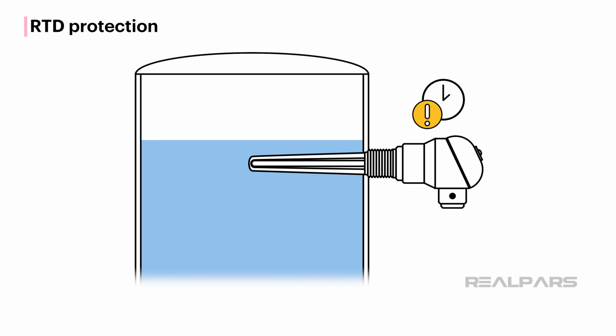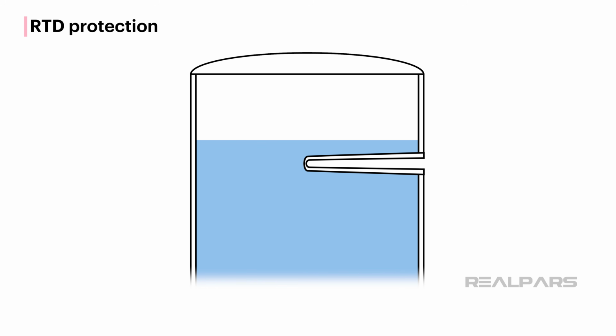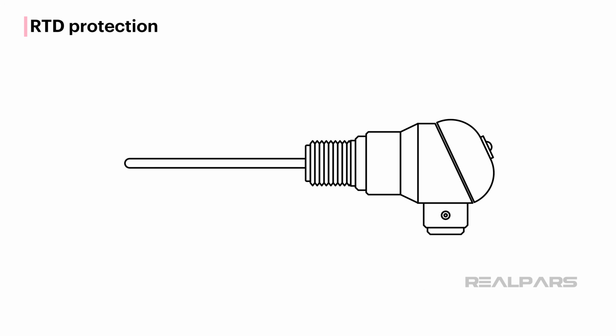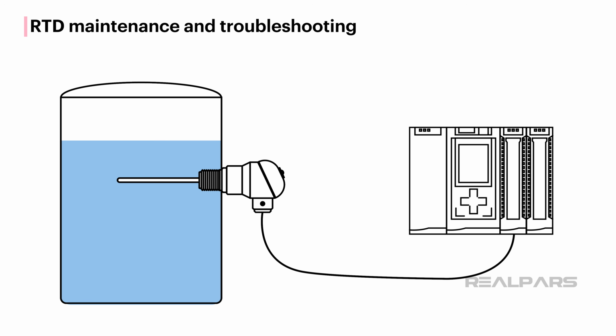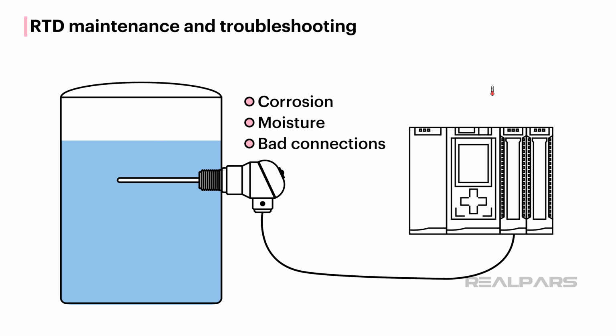Thermowells create issues, such as a delay in detecting process temperature changes. Thermowell placement is also an important consideration. Questions arise, such as, where do we place the thermowell in the pipe or vessel, and is the thermowell long enough? Let's talk briefly about RTD circuit maintenance and troubleshooting. Like any instrument or sensor in an industrial environment, problems arise due to corrosion, moisture, and bad connections. Any of those conditions will cause the temperature indications at the receiving device to appear abnormal or erratic. Of course, a defective RTD will cause issues as well.